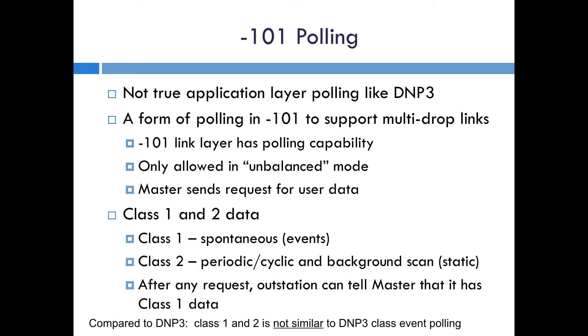Another function discussed in this specification is polling, though polling is a little bit of a misnomer. There's no real application layer polling like there is in DNP3. The polling they're referring to here is to support multi-drop links for IEC 60870-101. It is the link layer which is doing this polling — only for the unbalanced mode where the master is requesting user data at the link layer, basically telling the outstation to send anything it has. This allows the 101 unbalanced mode outstation to send data as it has it. It defines this as class 1 and class 2 data: spontaneous or event data is class 1, and class 2 data is the cyclic or background static data.